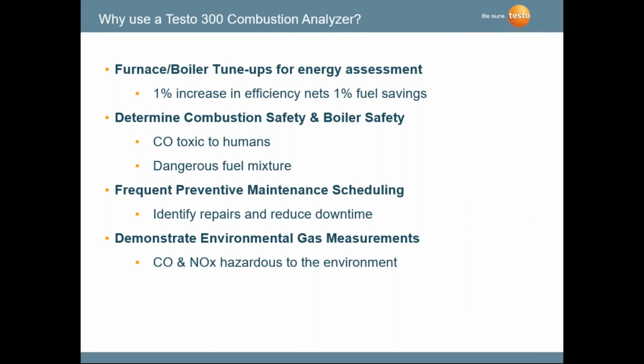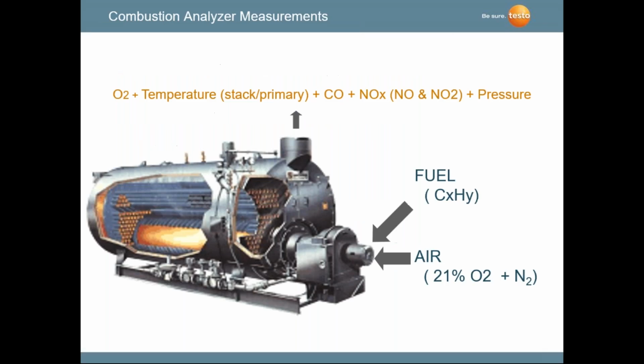And now we're getting into the heating season. I want to talk to you about combustion analyzers. And like I said, not everybody's into the season yet. We got people from all over the country here, but this is something that's on the top of our list as we start doing preventive maintenance and predictive maintenance on boilers and furnaces. We use combustion analyzers so we can look at fuel savings. We use combustion analyzers for safety, primarily carbon monoxide concerns, identify repairs and reduce downtime, preventive maintenance scheduling. We also look at NOx and CO for environmental gas measurements.